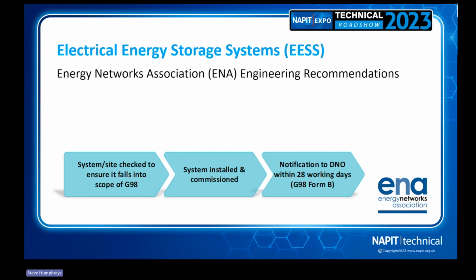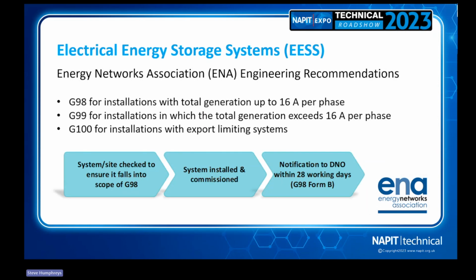Another consideration, which does apply to solar PV as well - if we look at the ENA engineering recommendations, the Energy Network Association, they'll have these notification guidelines. So something like G98, for instance - it's not an exact rule - that is generally for installations with total generation up to 16 amps per phase.